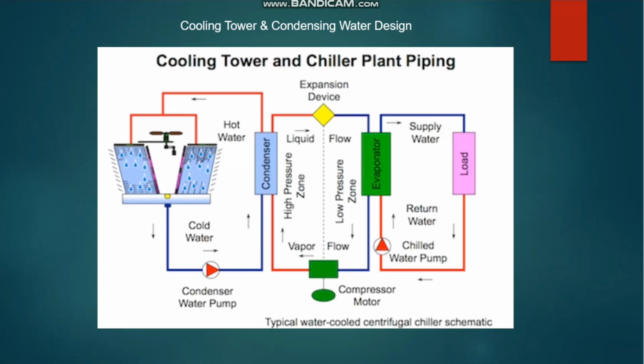Good morning friends. In today's video, we are going to see some important points related to cooling tower and condensing water design. The cooling tower is an open loop system. That means from the cooling tower, the cold water is supplied to the chiller using the condenser water pump. In the chiller, we have four main components: compressor, condenser, expansion device and evaporator. After the cold water is supplied to the condenser, I mean the chiller, the hot water comes back to the cooling tower, where it is openly dropped. That is why it is called an open loop system.